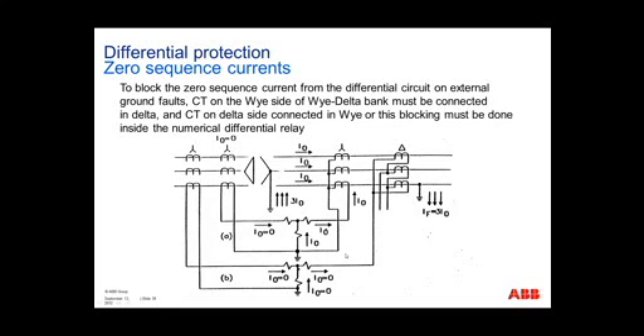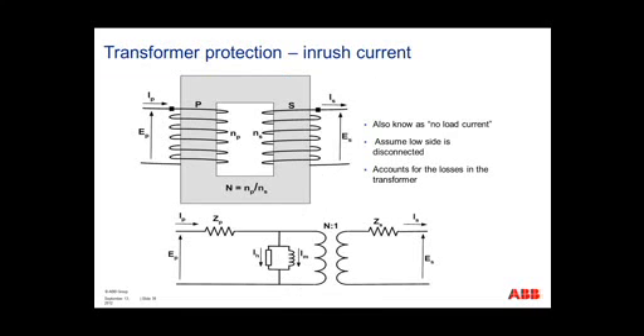Once again, this is using solid state relays. If you were using a microprocessor-based relay, you can use a Y connected CT on the Y side. Use your settings inside the relay to filter out your zero sequence currents.